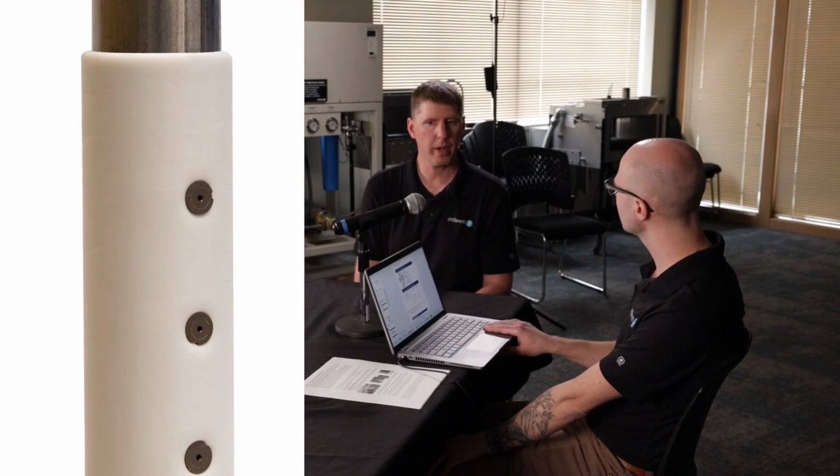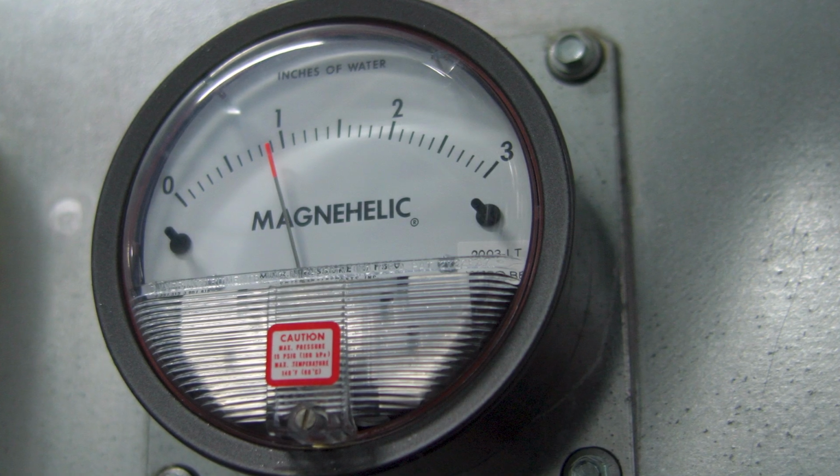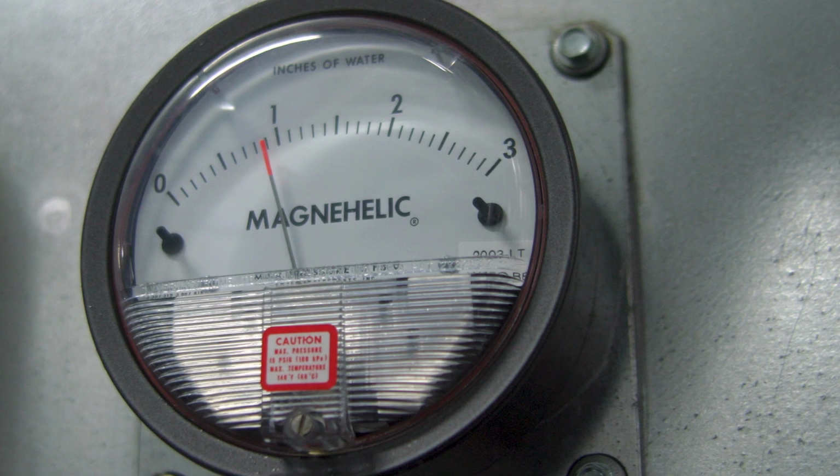Some of the key things is we talked about efficiency. We want to keep it steam as much as possible, and so you want to reduce those inefficiencies as much as possible. We mentioned insulation as an example. That's a key way to keep the tubes hot so it's not going to collapse back. We have to think through how long it is going to take for that steam cloud to dissipate. That's another key piece. And then we have to think through the air pressure drop. If you add more tubes, are you adding more pressure drop? To a degree, depending upon how they're shaped. So you're trying to balance on those different things.